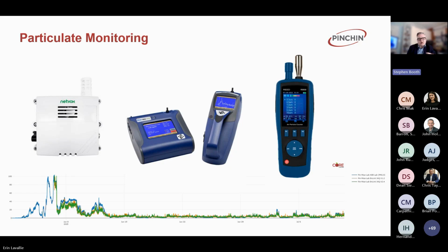On the left-hand side of the screen is a continuous reading instrument. These can be installed at various locations throughout the building, outside the building, inside air intakes, and in various occupied spaces on the floor, providing a continuous reading of PM 2.5 concentrations. In addition, there are a variety of handheld instruments that building operators can deploy prior to and during an event to monitor how the situation's going, and potentially to know when they could start removing procedures.